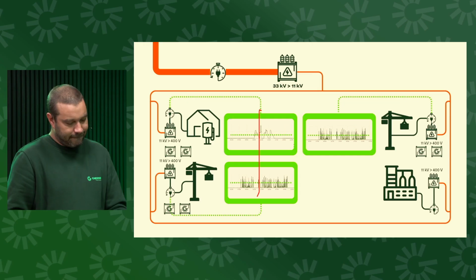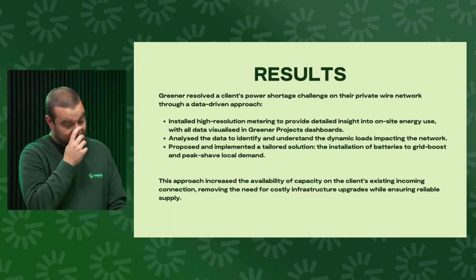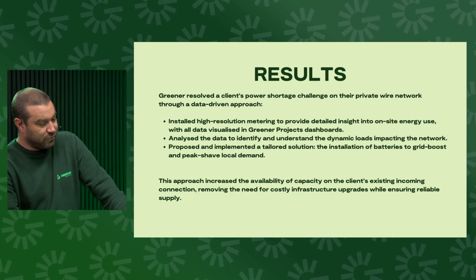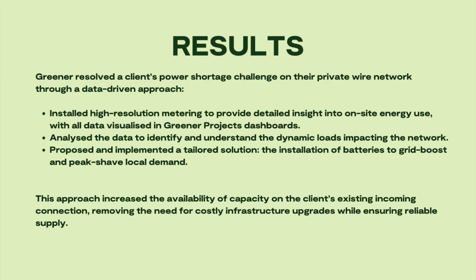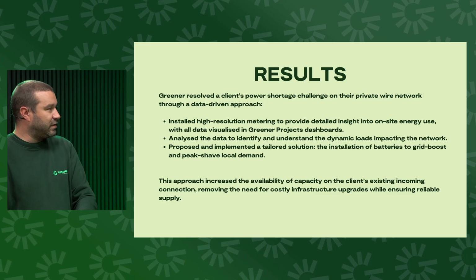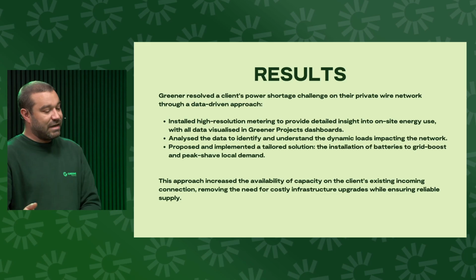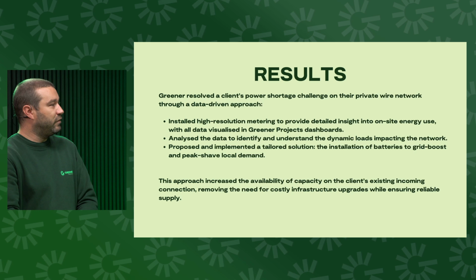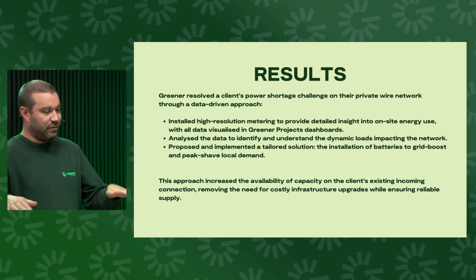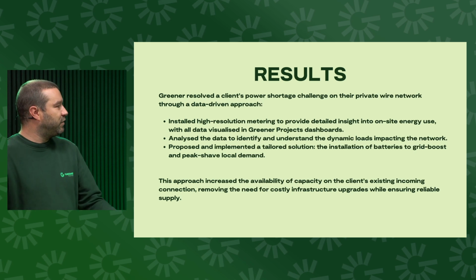So to finalise this case and its results, we were able to solve the client's power issue, their power shortage, by installing metering to understand what was going on at the site, and then, through that data-driven approach, fitting batteries to do peak shaving, which really alleviates the requirement for them to have a grid upgrade because they've just managed the energy they've already got on site.